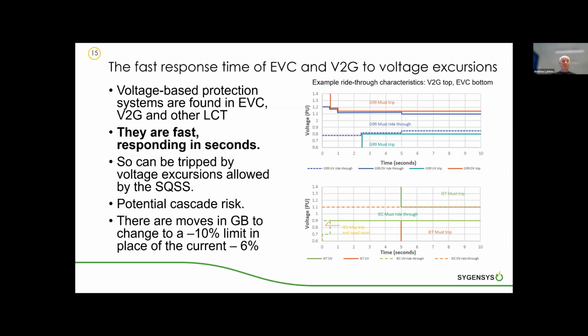And the thing to realise is that electric vehicle chargers and vehicle-to-grid systems are sensitive to voltage excursions. Specifically, EV chargers in some respects are a new class of load, where they include both under-voltage protection and over-voltage protection. And they can be fast responding. So typical response times to under and over voltage conditions, depending on the scale and size of those excursions, can be within a matter of seconds. And that is well within the limits which are allowed within the quality standard SQSS.